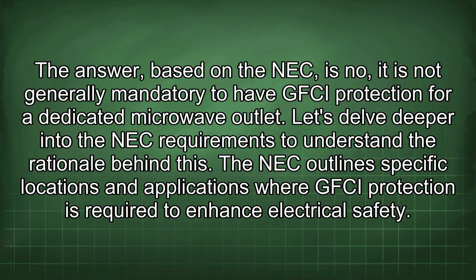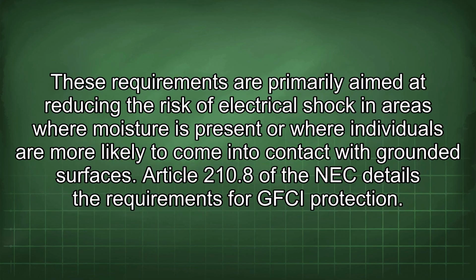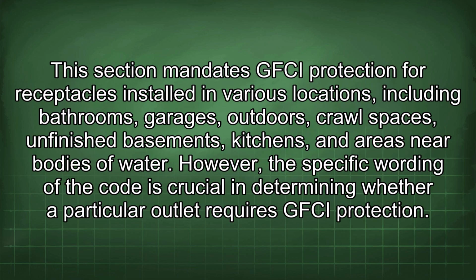The NEC outlines specific locations and applications where GFCI protection is required to enhance electrical safety. These requirements are primarily aimed at reducing the risk of electrical shock in areas where moisture is present or where individuals are more likely to come into contact with grounded surfaces. Article 210.8 of the NEC details the requirements for GFCI protection. This section mandates GFCI protection for receptacles installed in various locations, including bathrooms, garages, outdoors, crawl spaces, unfinished basements, kitchens, and areas near bodies of water. However, the specific wording of the code is crucial in determining whether a particular outlet requires GFCI protection.